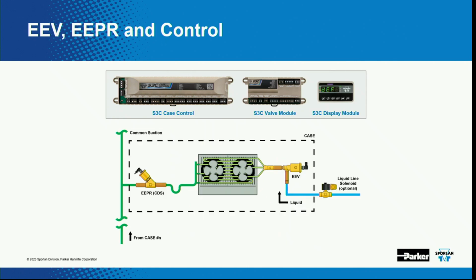But we can also use an EPR or an EEPR, a dedicated pressure regulator, to control our pressure on that coil. And the way we would do that is, in this case, the stepper motor is going to be controlled with the main control module, and then the EEPR is going to be controlled with the valve module. But you need to make sure there's some dip switches on the left side of that board, and you've got to flick the first dip switch down. We've got more on the specific setup of this, but that will tell it that this valve module is controlling an EEPR, not an EXV or an EEV.